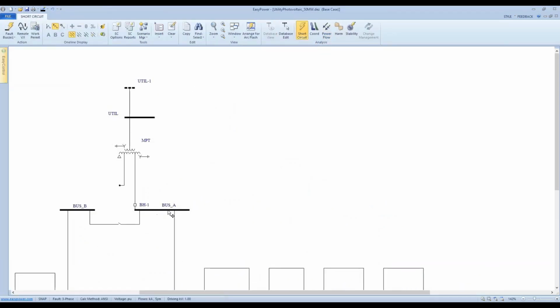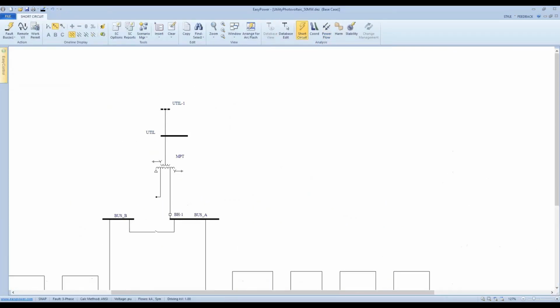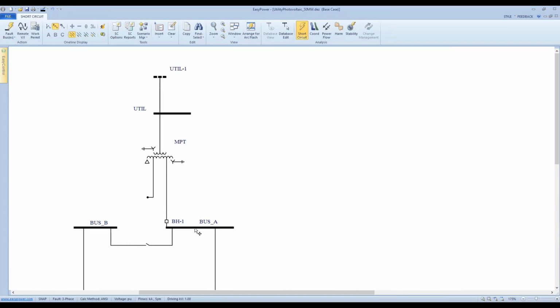Apply a fault here, bus A, because that's the low end of the main power transformer, right? Same location. So apply the same fault, three-phase ground. How much current did I get in total? Do the math. 348 from B plus 522 from A. I got 870. What did I get from my equivalence model? 870. Okay, perfect. Total fault current, 9,073. 9,073. It's exactly the same.